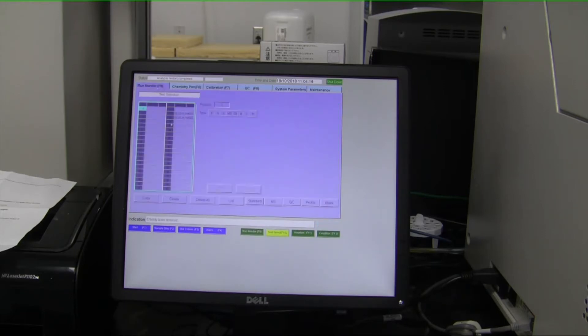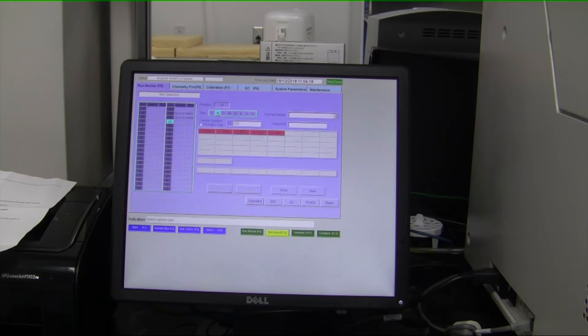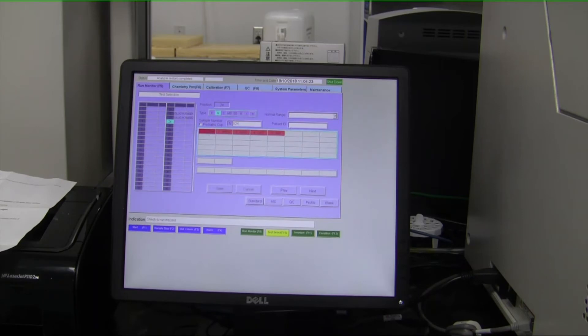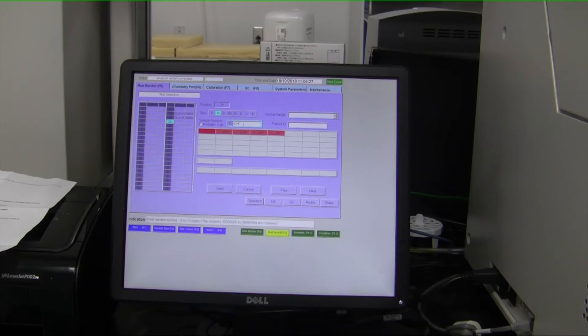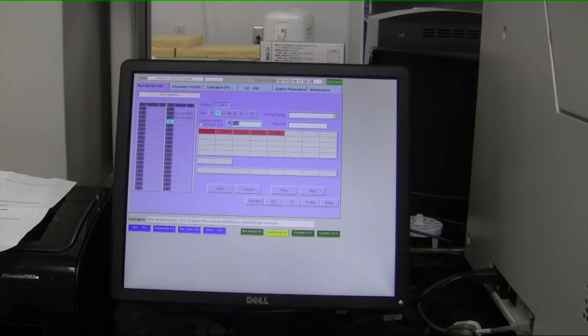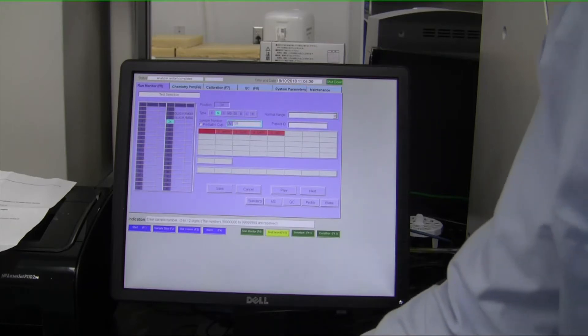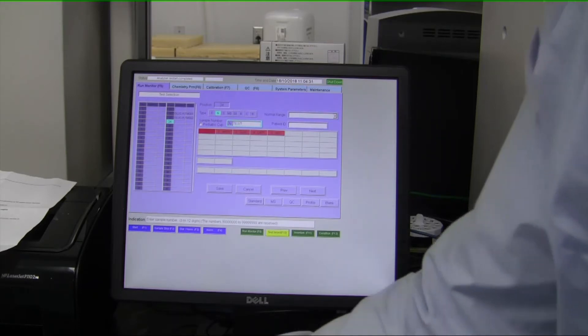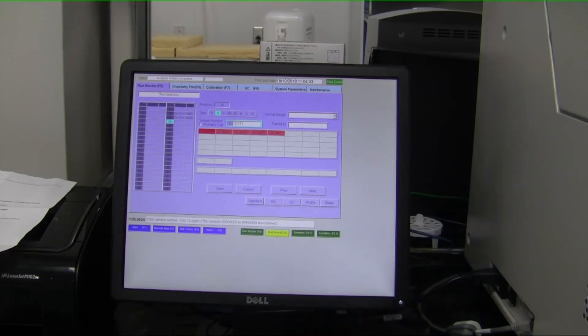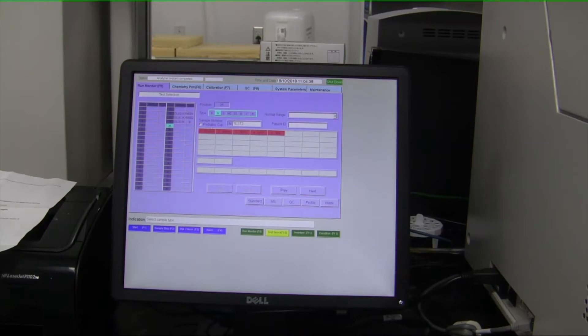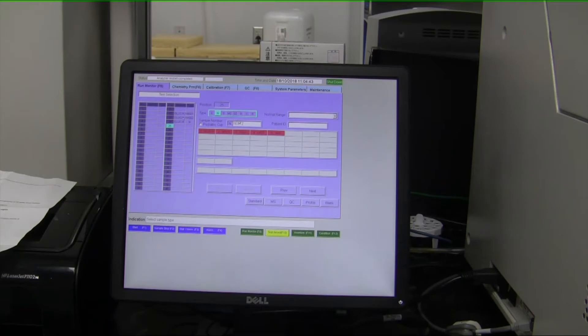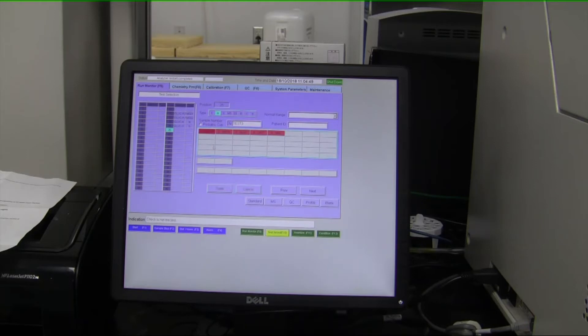Once you have all that loaded, you can go to the next position. Let's say, for example, we wanted to run a normal sample type and we wanted to run it for glucose. Here we can name the sample—let's just say we wanted to name it test one. Then when you save the position, you can see it automatically goes to the next position and it's ready for you to load the next sample and automatically increases the last digit from one to two. So it sequentially names the sample, and then you would just have to select your metabolites and click save. So it's essentially two buttons to run the samples.